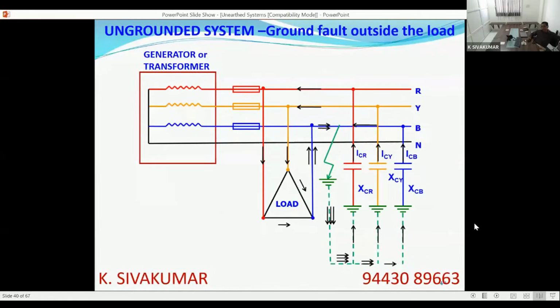If you can see this circuit, in this circuit also the fault is not in the equipment. The fault is outside the equipment in the network cable or the network line. You can see here also the load impedance is introduced in the ground circuit. You can see the current flow diagram. But how the capacitor is now discharging into the fault, it introduces one more impedance. Apart from the capacitive reactance, it introduces one more impedance in the circuit. Depending upon the type of the load, it may be a resistive impedance or an inductive impedance or a capacitive impedance also. There are three possibilities or a mixture of all the three.